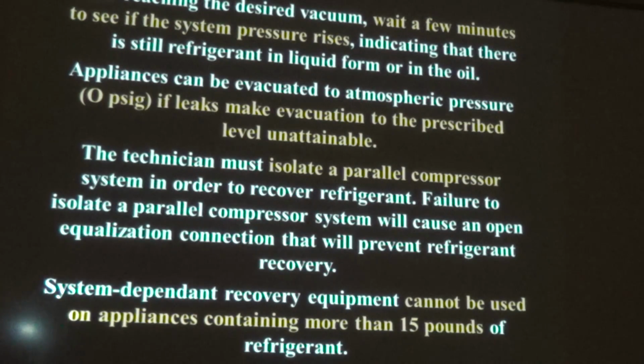Once you get to the desired level of vacuum, you're going to valve off the system and see if pressure rises. It indicates that there's still refrigerant in liquid form or in the oil. Appliances can be evacuated to atmospheric pressure only if they have too many leaks, because leaks make evacuation to the levels we talked about before impossible. If we have a hole in the system, we're not going to get it to 4 inches of vacuum, 10 inches, or 15, because it's never going to go anywhere but to 0, because the atmosphere is coming in. So if you can only get to 0, then that's fine. That's as far as you can go.